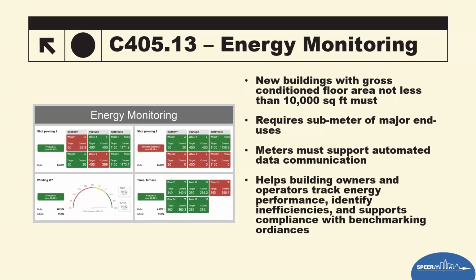And then energy monitoring continues to tighten up requirements, lowering the building size threshold from 25,000 square feet to 10,000 square feet. This means a much wider range of commercial buildings must now install metering or monitoring devices that capture energy usage by end use. That includes HVAC, lighting, EV chargers, things like that. Importantly, the code expects this data to be available in a usable format, hourly or better, and enables benchmarking, performance tracking, and operational optimization.